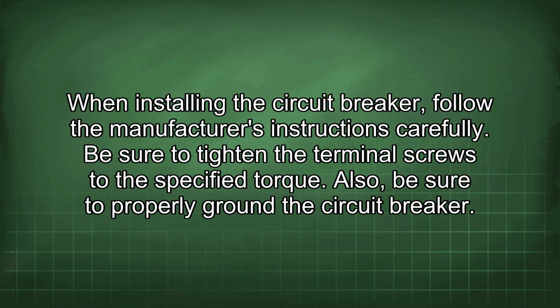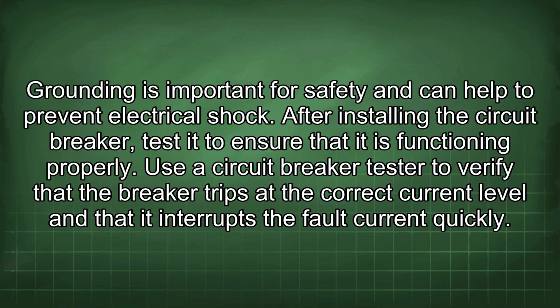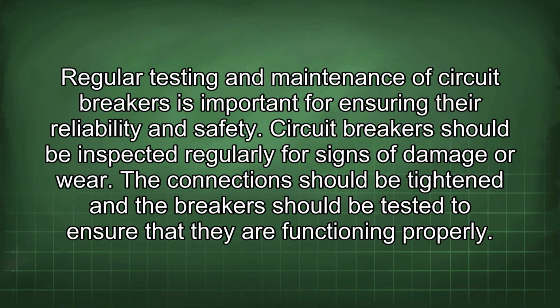When installing the circuit breaker, follow the manufacturer's instructions carefully. Be sure to tighten the terminal screws to the specified torque. Also, be sure to properly ground the circuit breaker. Grounding is important for safety and can help to prevent electrical shock. After installing the circuit breaker, test it to ensure that it is functioning properly. Use a circuit breaker tester to verify that the breaker trips at the correct current level and that it interrupts the fault current quickly. Regular testing and maintenance of circuit breakers is important for ensuring their reliability and safety.